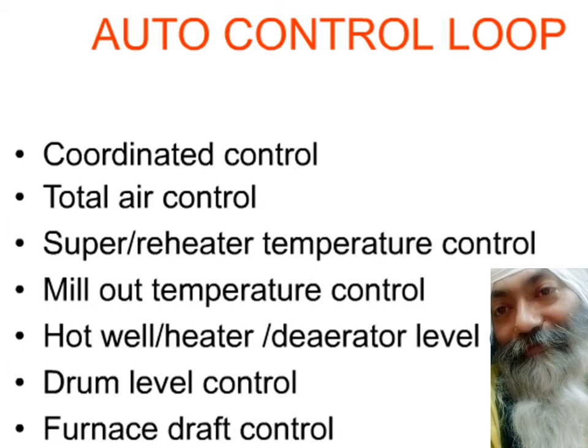Using DCS, we can implement auto control loops including coordinated control, total air control, superheater and reheater temperature control, mill outlet temperature control, hot well, heater, and deaerator level control, and drum level control. Operators can control all these at the click of a button, including furnace draft — the amount of air entering the furnace in a controlled manner.